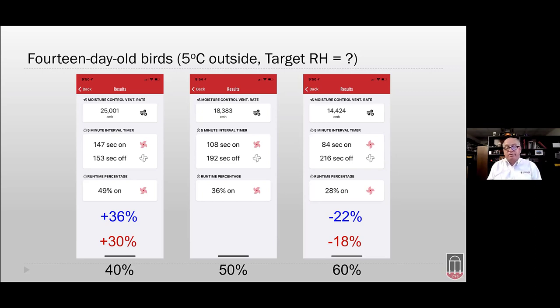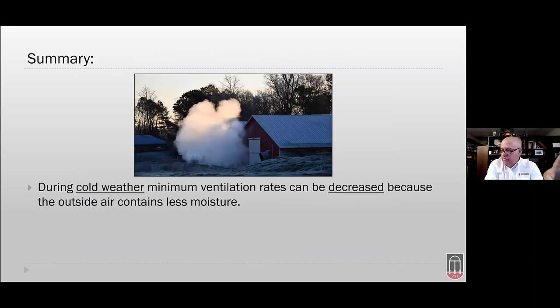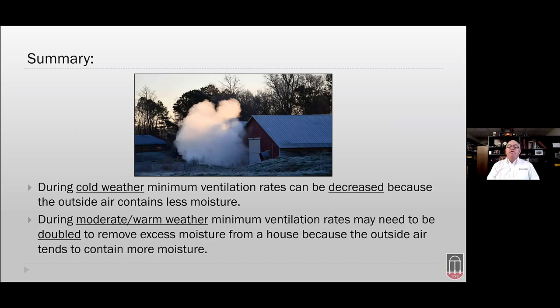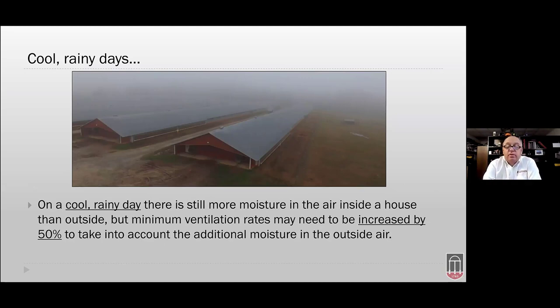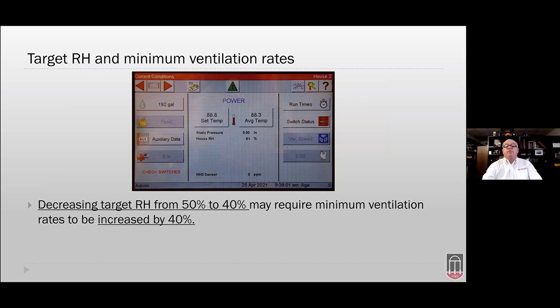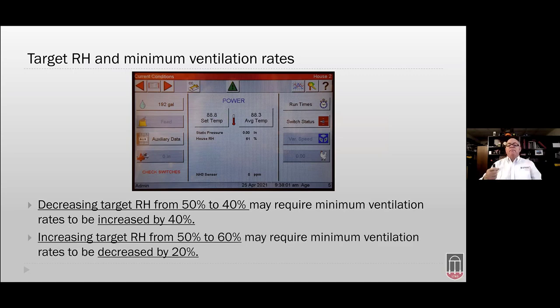In summary: during cold weather, minimum ventilation rates can be decreased because outside air contains less moisture. During moderate to warm weather, minimum ventilation rates need to be doubled to remove excess moisture. On cool rainy days, rates may need to increase 50-100% to account for additional moisture in outside air. Decreasing the target humidity from 50% to 40% may require a 40% increase in ventilation rate. Increasing the target from 50% to 60% may allow a 20% decrease in ventilation rate.